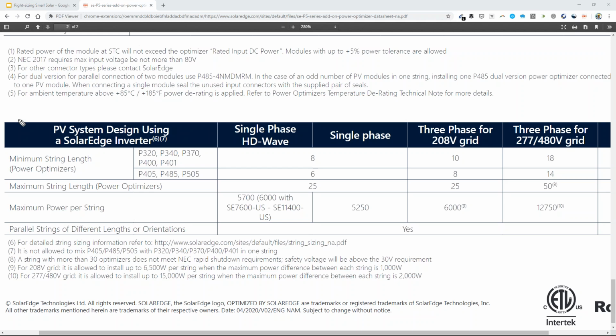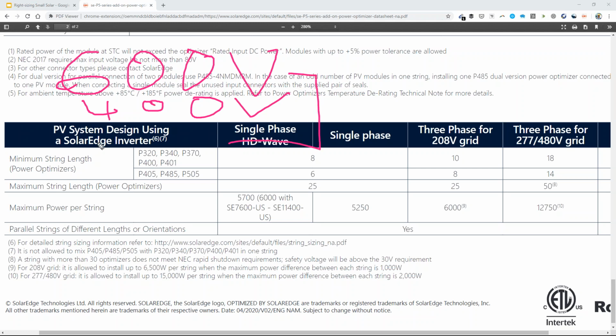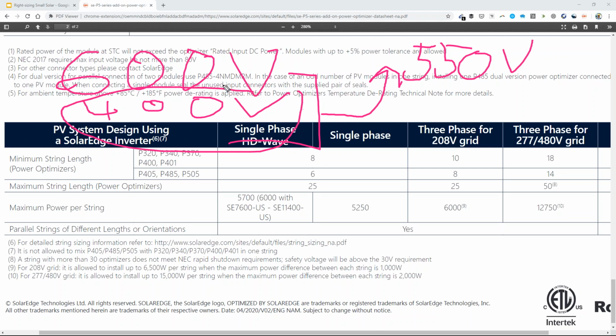Earlier we said solar arrays are designed around 600 volts, but maybe due to temperature degradation they're only operating at 400 volts during max power. What the SolarEdge platform does is control the voltage of every single panel on that circuit and step the voltage back up—correcting from 400 volts and increasing the output voltage of the circuit, which decreases the amperage of the circuit.